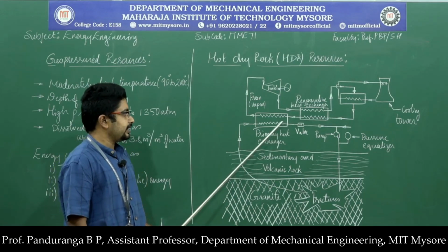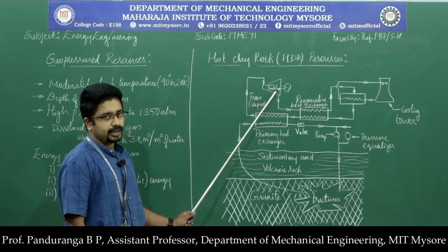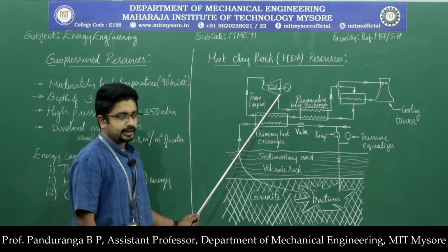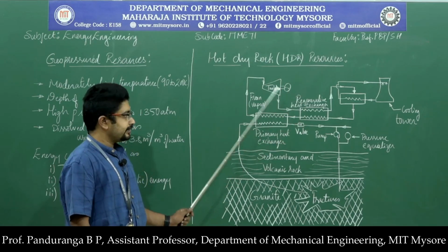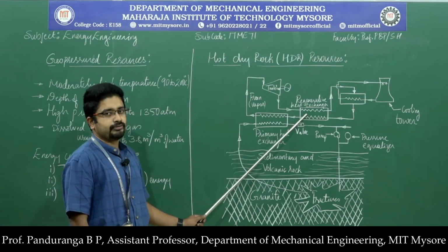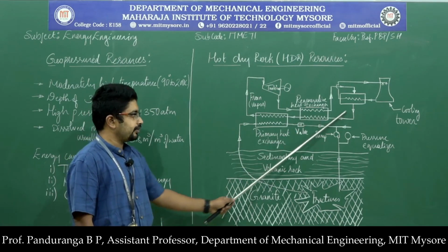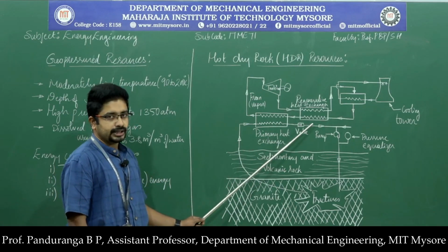Once the heat is transferred to the Freon, it becomes vapor and passes through the turbine, converting heat energy into mechanical energy which is coupled to a generator producing electrical energy. Then that Freon, which will be at a slightly higher temperature, can provide energy to the liquid Freon coming out of the condenser. For that purpose we have the regenerative heat exchanger.